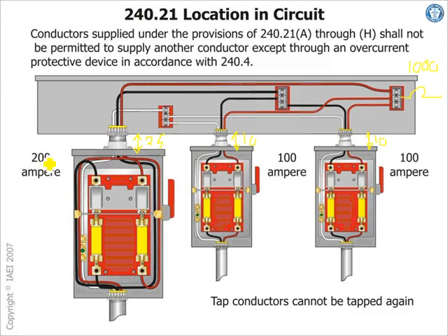25, 3 times, to tap 200 amp, how much does this circuit breaker have to be? 600, right? So which one is going to rule then? The 25 is going to rule, so that cannot be 2,000. It has to be 600. Can you guys see that? So I take a 600 amp here, tap it with 1/3, give me 200, and then tap it with 1/10. 1/10 of 600 is 60 amp, the smallest that I can tap.